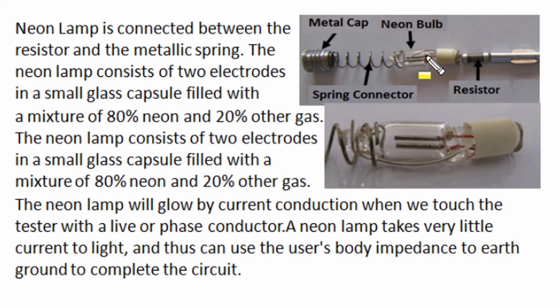The sensitive neon bulb is the key component of the line tester, and it is connected between the spring connector and the high value resistance. In this test circuit, a neon lamp has two electrodes with a small displacement in a glass enclosure in which we fill a gas mixture of 80% neon and 20% other compositions. When a small voltage difference comes across these two electrodes, an arc will strike between the two electrodes, and that discharge in the neon environment produces a characteristic glow around the neon lamp.